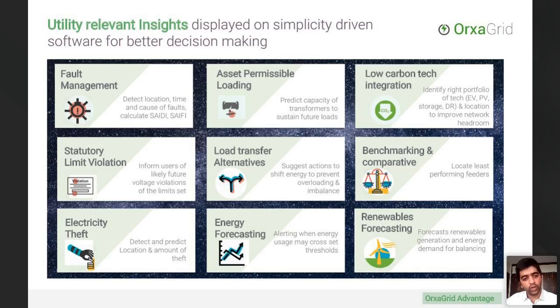Other insights mainly on the load transfer alternative. This is a traditional distribution management, like a SCADA DMS option, where if you're monitoring multiple feeders in a vicinity, you can understand whether a particular feeder or asset is overloaded while other assets are underloaded, and whether the grid network can allow for transferring some of the load from an overloaded line to an underloaded line, and so on.